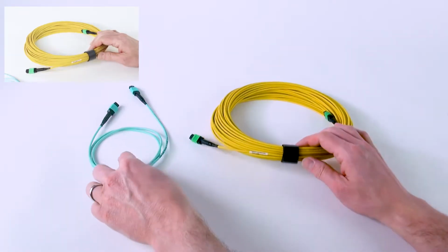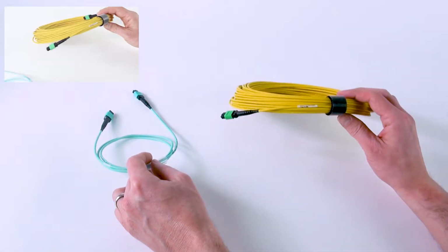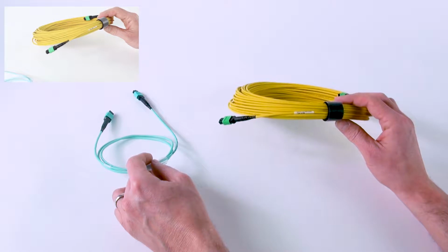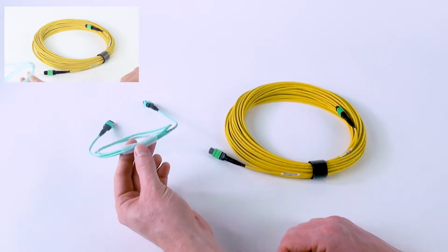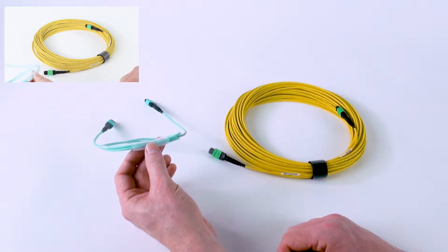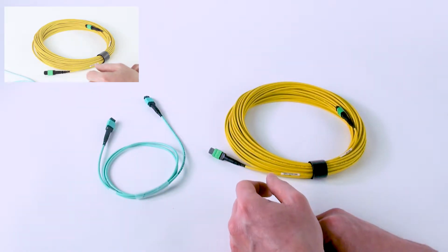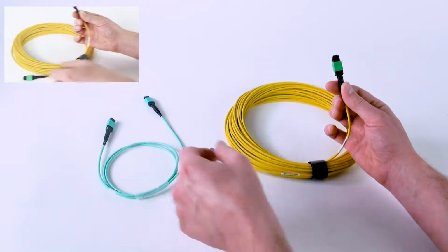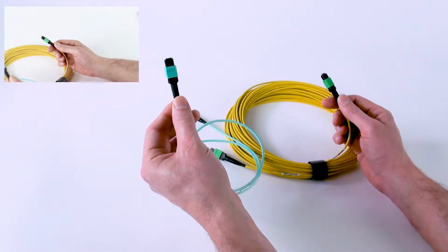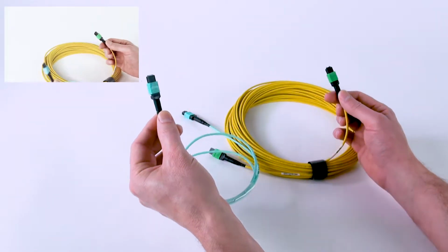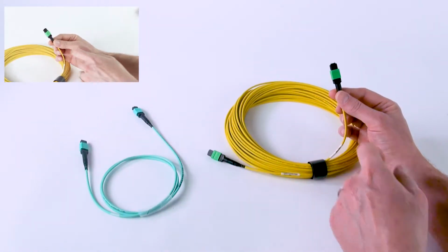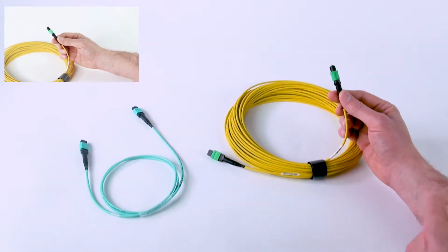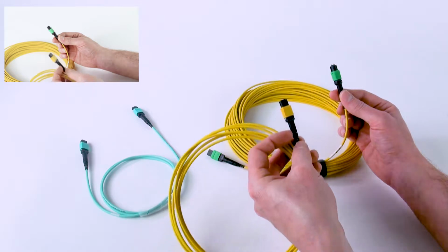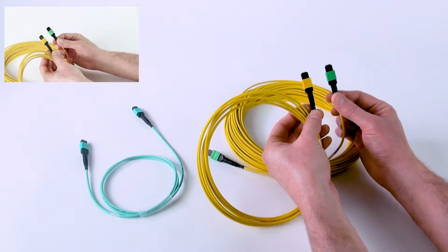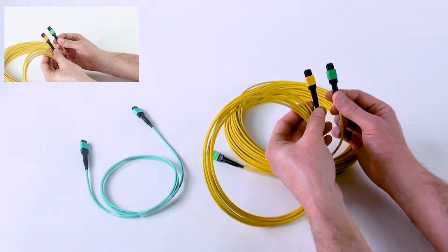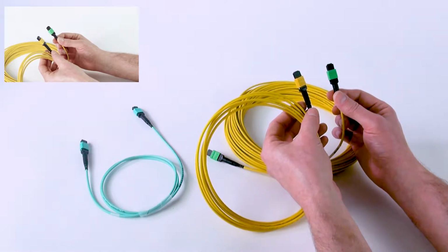The first is the color of the jacketing itself. On the right here is the yellow jacketing, which indicates single mode MPO fiber. On the left is the aqua jacketing, which indicates multi-mode. The next is the color of the connector itself—on this multi-mode connector I have the aqua color that matches the jacket, and on the single mode connector I have this green color that indicates it's APC. You'll oftentimes see single mode fiber with a yellow connector interface as well. Both of these indicate that you're working with single mode fiber.